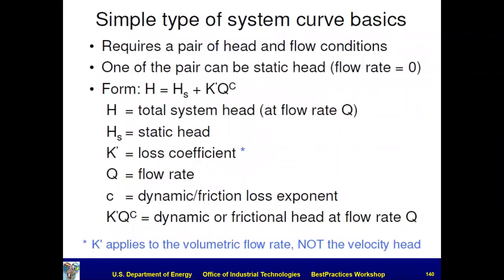Okay, so here's a simple system curve. So you see the form: total head required at a given flow rate is a static head plus this K prime, and this is a loss coefficient. This is unique to the system curve. I mean, we use K's all over the place, so this isn't the previous K that we had for a valve loss coefficient, K times V squared over 2g. It's not that K. This is K prime. It's a different K. Just like H gets used all over the place, enthalpy and convection coefficient and all that.